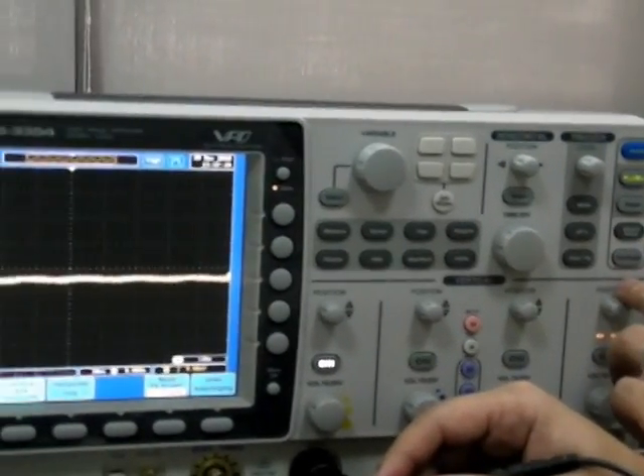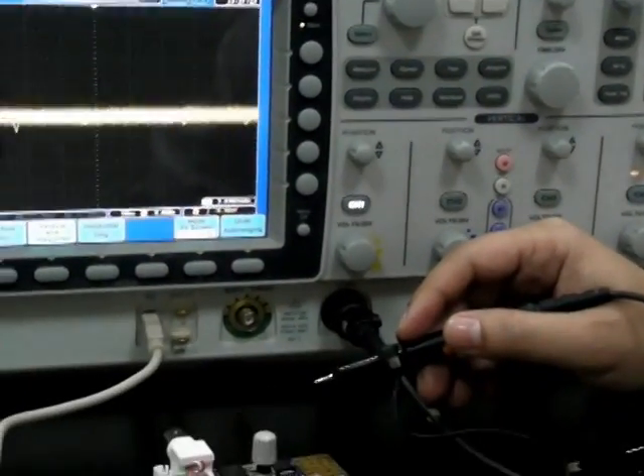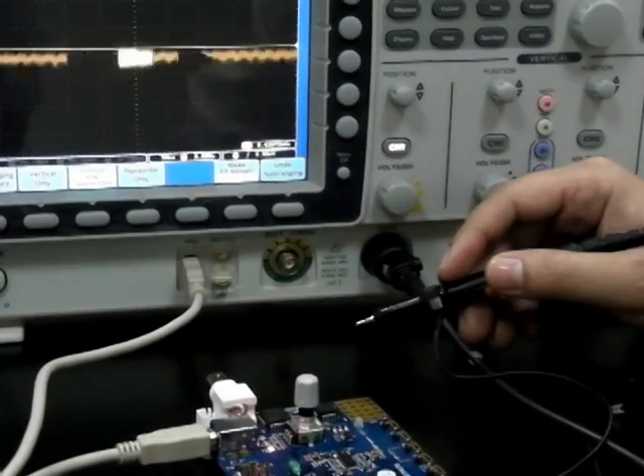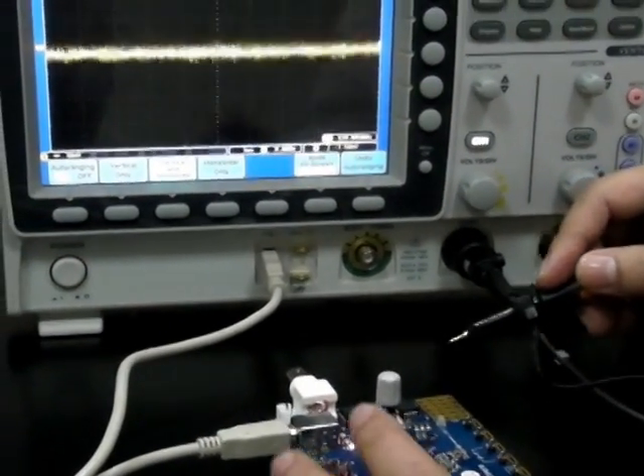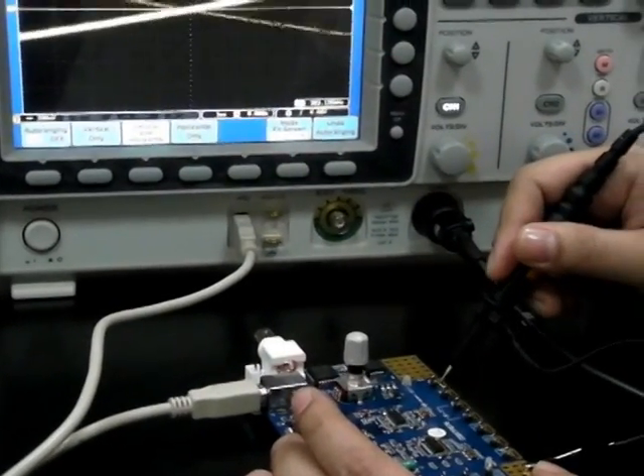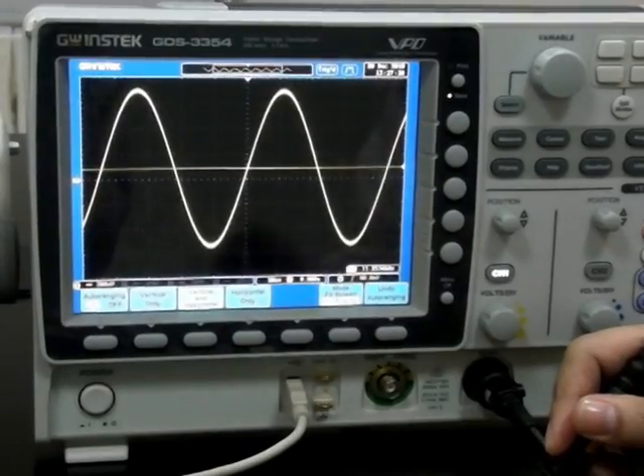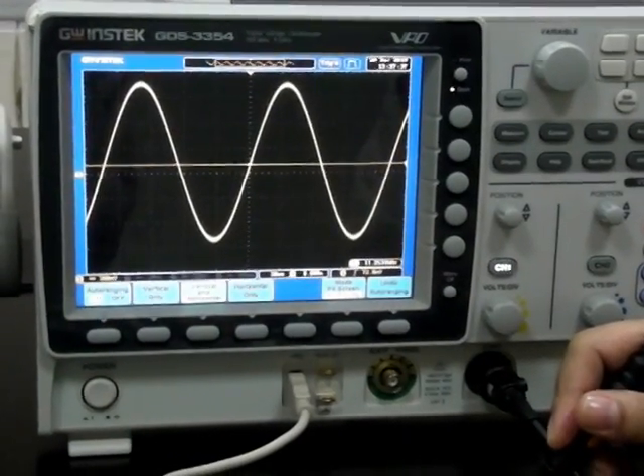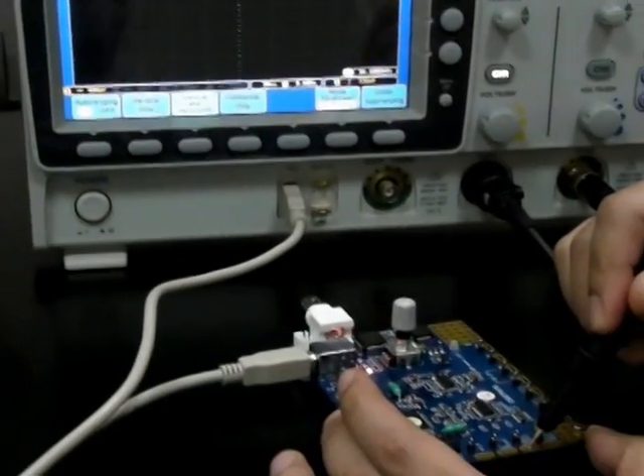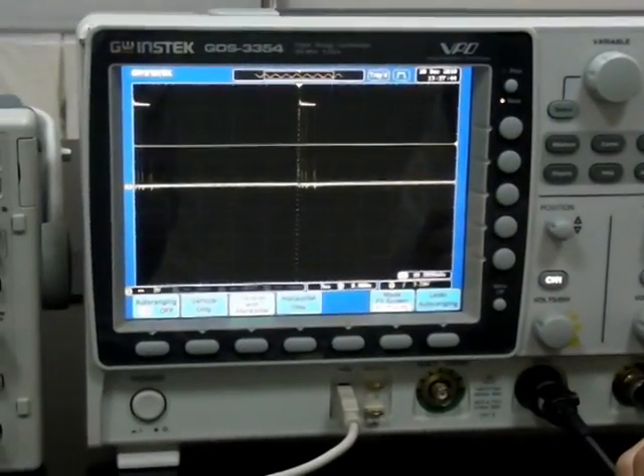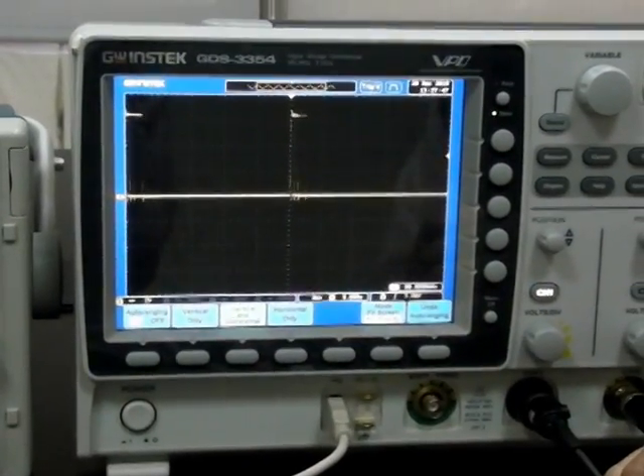In addition to the above two features, the TDS-3000 also lacks the GDS-3000 auto range function. The auto range function has the capability of automatically adjusting a signal to the ideal scale. For example, if a sine waveform and burst waveform are measured consecutively, the vertical and horizontal ranges will automatically scale to suit each waveform. When using the auto range function, waveforms are displayed on the screen at the best possible scale.